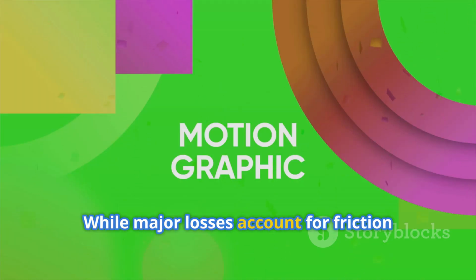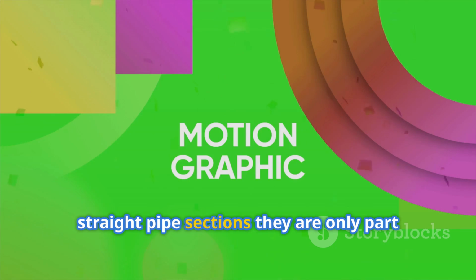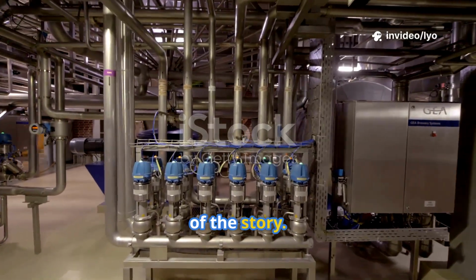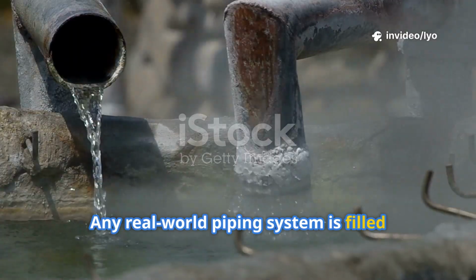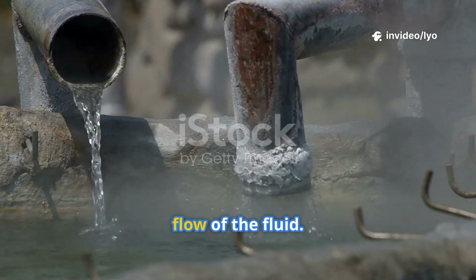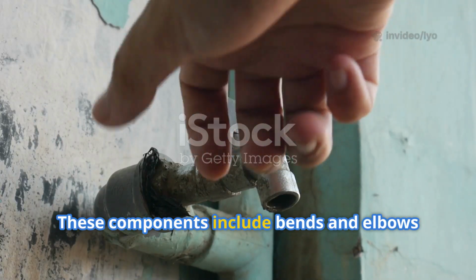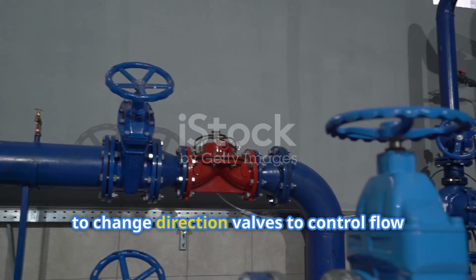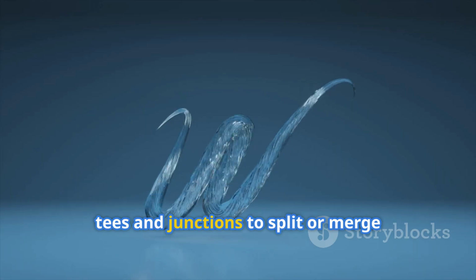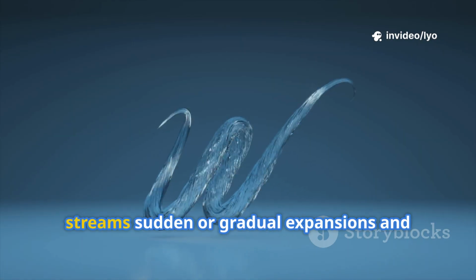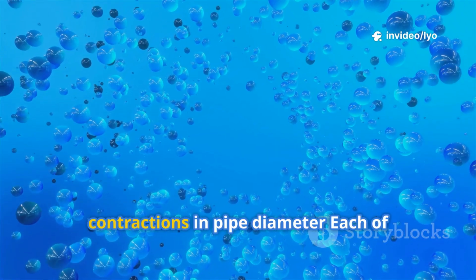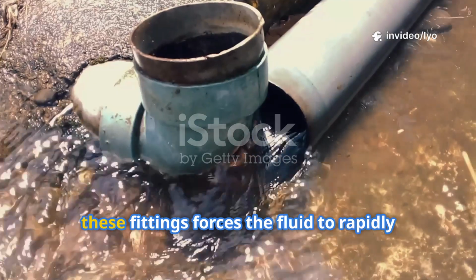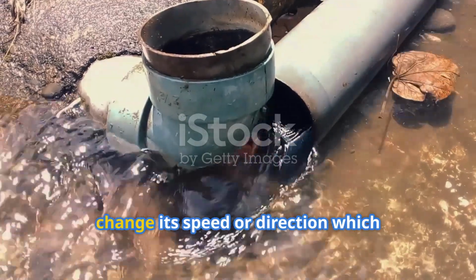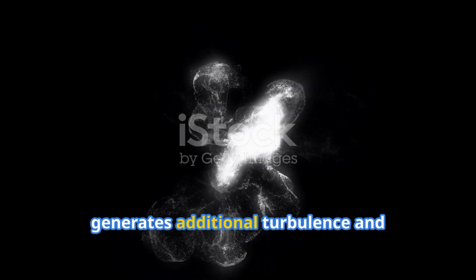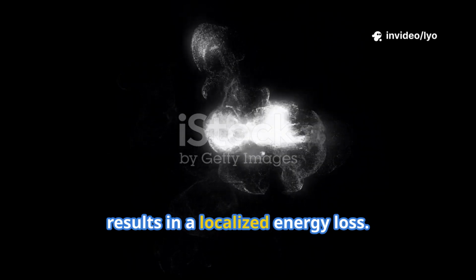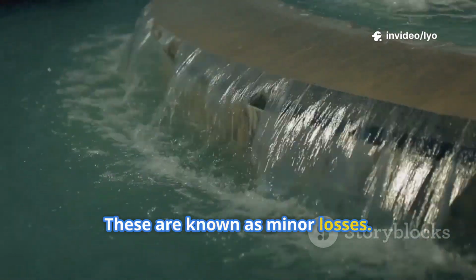While major losses account for friction over long, straight pipe sections, they are only part of the story. Any real-world piping system is filled with components that disrupt the smooth flow of the fluid. These components include bends and elbows to change direction, valves to control flow, tees and junctions to split or merge streams, and sudden or gradual expansions and contractions in pipe diameter. Each of these fittings forces the fluid to rapidly change its speed or direction, which generates additional turbulence and results in a localized energy loss. These are known as minor losses.